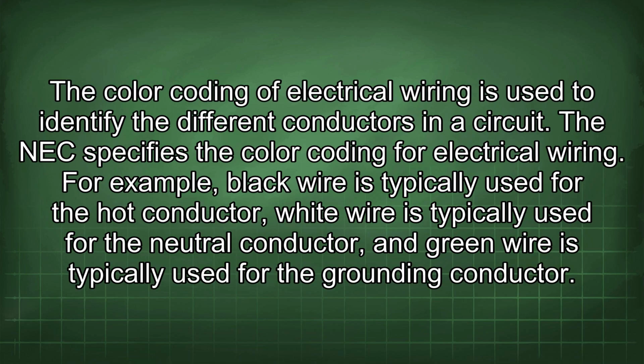The color coding of electrical wiring is used to identify the different conductors in a circuit. The NEC specifies the color coding for electrical wiring. For example, black wire is typically used for the hot conductor, white wire is typically used for the neutral conductor, and green wire is typically used for the grounding conductor.